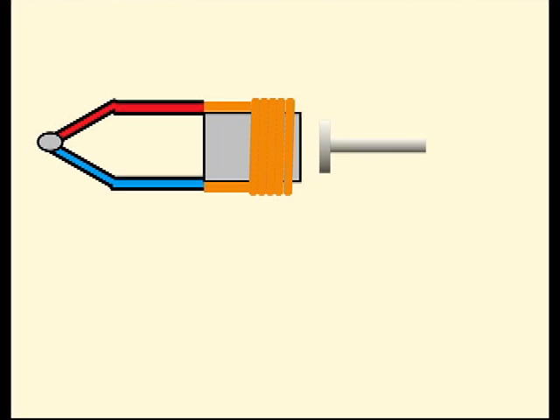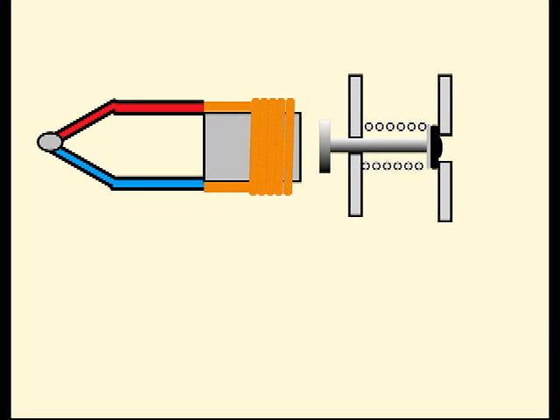Close to the ferromagnetic core is a small iron plate welded to a sliding shaft. At the other end of the shaft, there is a rubber gasket which rests against a hole through which the gas goes on to the input of the heater. A spring holds the rubber gasket covering the hole.